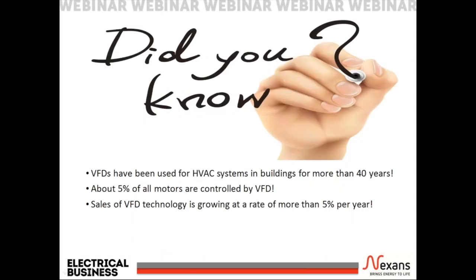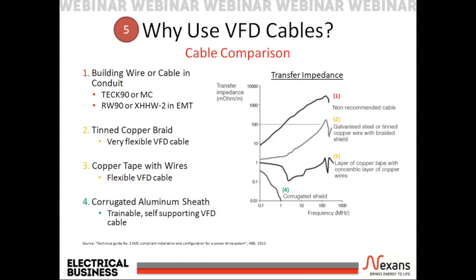Here are some interesting facts about VFDs. VFDs have been used for HVAC systems and buildings for more than 40 years. About 5% of all motors are controlled by VFD. Sales of VFD technology is growing at a rate of more than 5% per year. A good tool for comparison of VFD cable constructions is considering transfer impedance. This is a measure of the shielding effectiveness, or rather, the wide frequency range return path impedance.